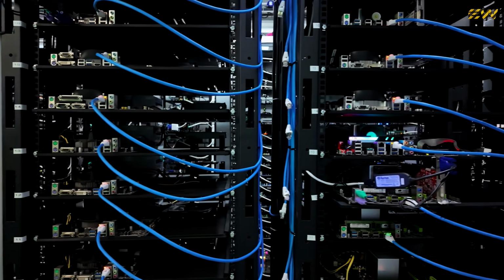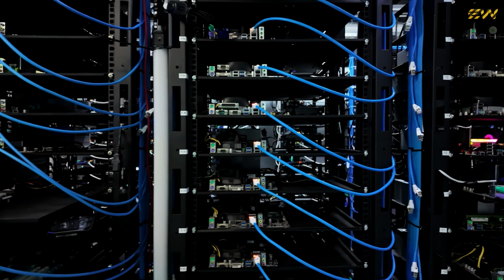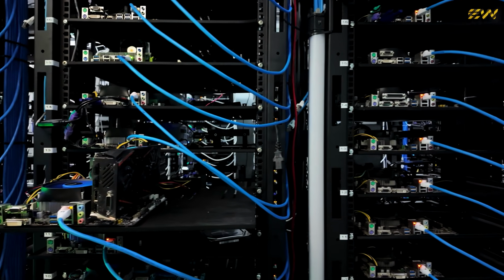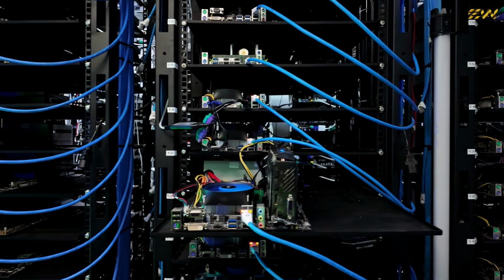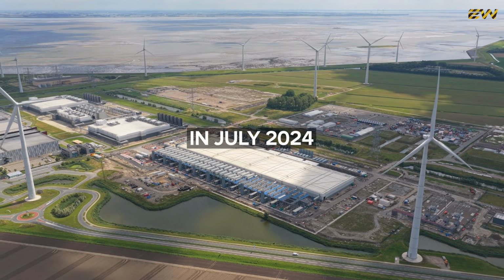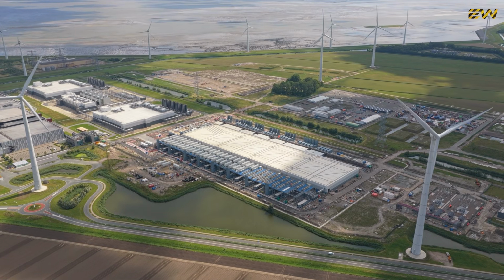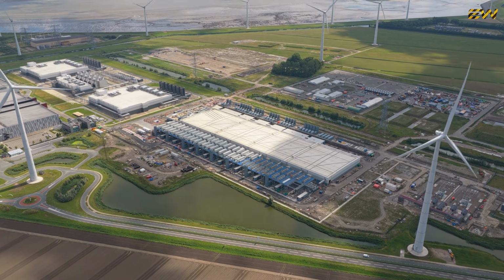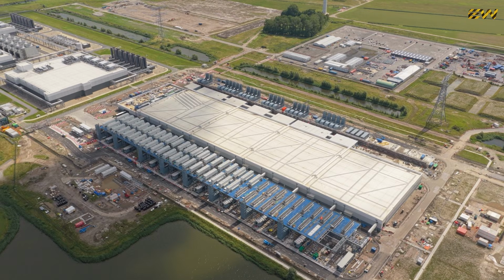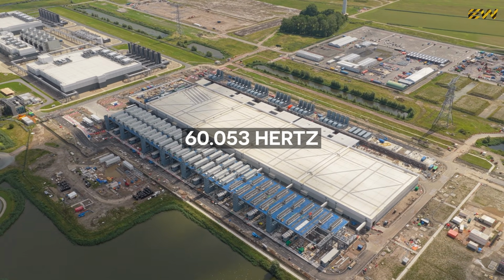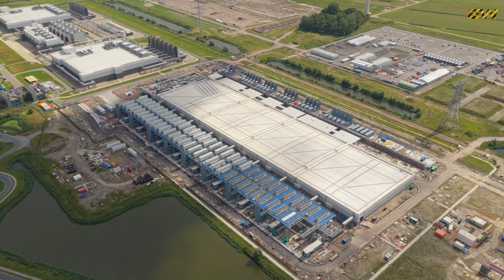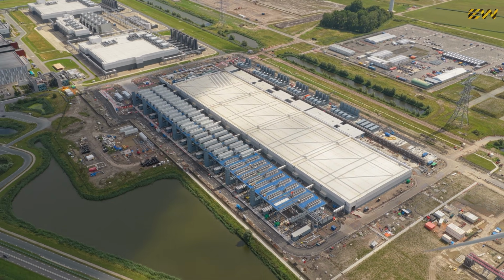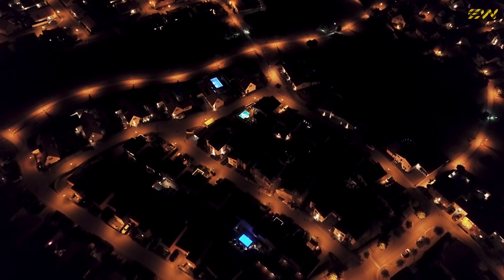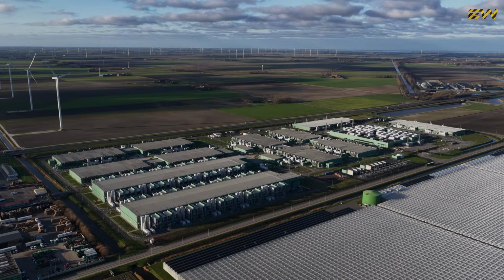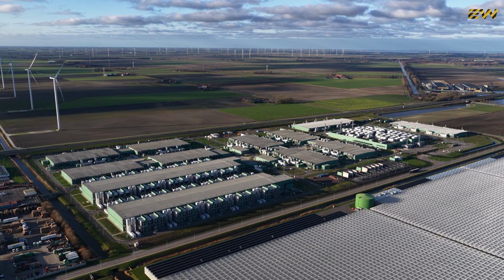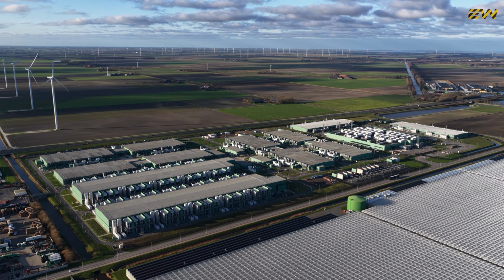To protect sensitive equipment, data centers drop off the grid, but if dozens disconnect at once, the grid suddenly experiences massive load loss. In July 2024, 60 data centers in Northern Virginia disconnected almost simultaneously. The grid saw a 1500 megawatt surplus. Frequency spiked to 60.053 Hz. That's a dangerous deviation. Grid operators must respond within seconds. Otherwise, cascading outages become possible. Data centers don't just consume electricity, they influence frequency stability.